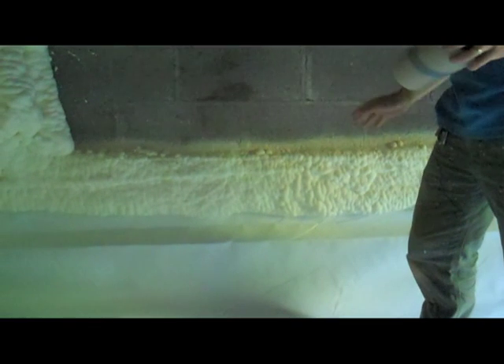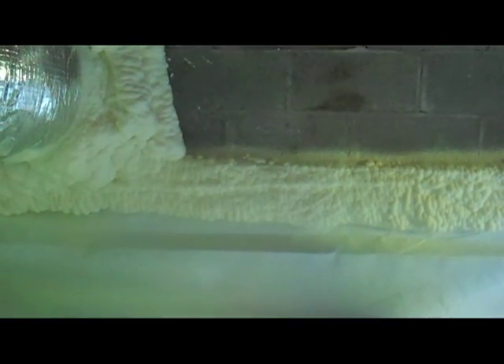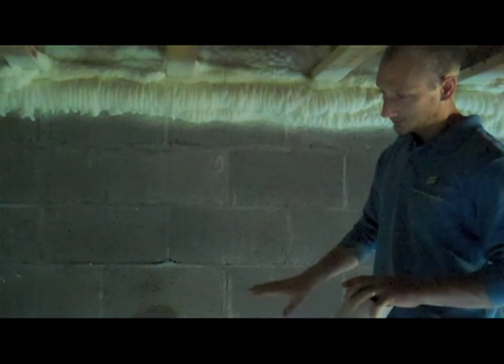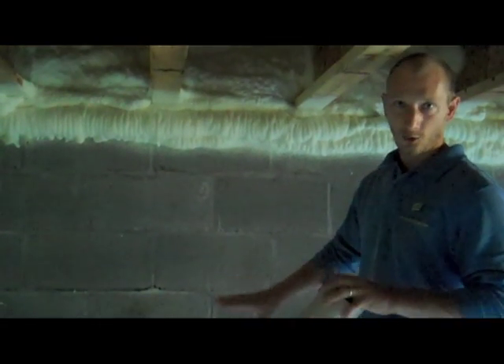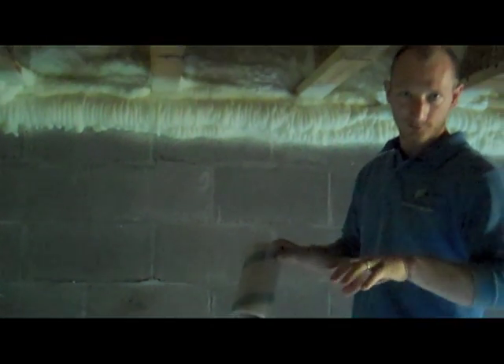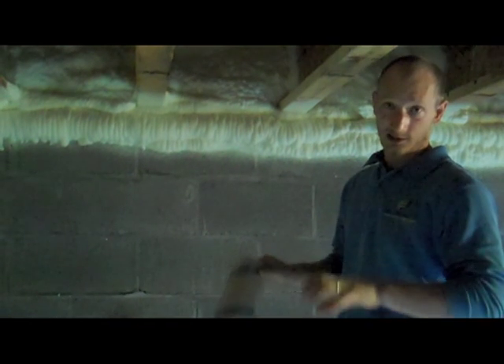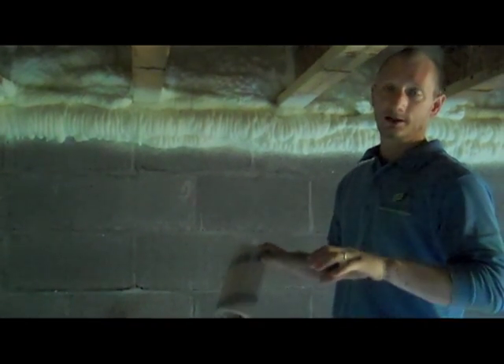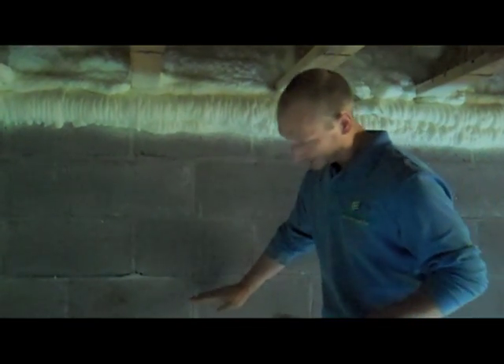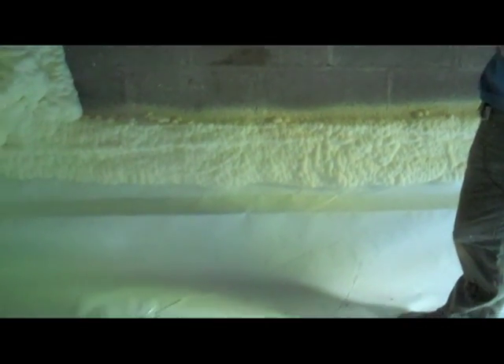Spray foam adheres to just about anything. It's a permanent, inert product, so unless someone comes in and physically removes it, it's not going to go anywhere — just another way to assure that this plastic always stays fastened. In a conditioned crawl space, the vapor barrier is the most important part of the entire crawl space because it's what's really controlling indoor air quality and also soil moisture. So you have to make sure that it's sealed appropriately. That's why we took it at least six inches up the wall. All of our seams are overlapped by 12 inches and then taped, again using a high-quality tape.